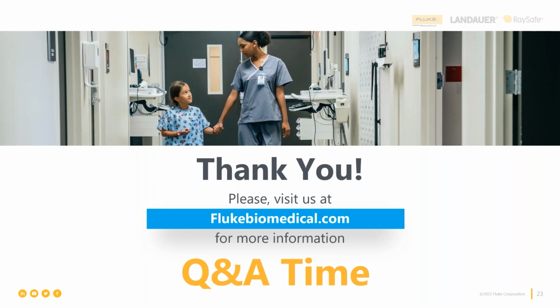The next question that came in was, how can I use an ESA to test the conductivity of the cleaning solution when testing ultrasound transducers? You actually cannot use a regular ESA. The only test instrument that we make that allows you to test conductivity of the cleaning solution is the ULT 800, and it is a pass-fail test. So you're not going to get any measurement values for conductivity. It is a simple test. It's just designed to make sure that the cleaning solution has not been too diluted, that it has been mixed properly, and therefore is able to carry the current flow and be part of our testing circuit.